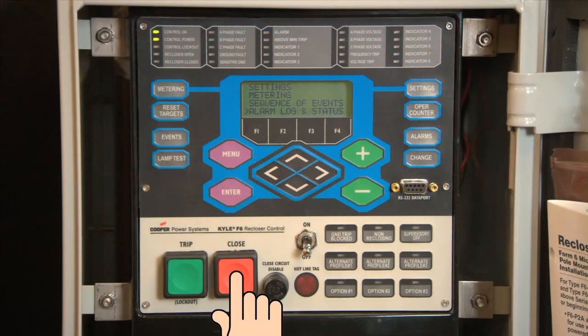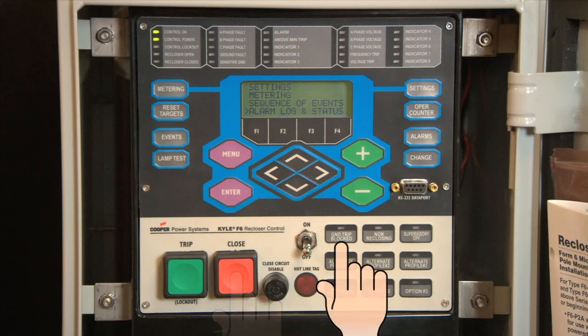Close Push Button. When pressed, the Close Push Button returns the control to the initial or home position, closing the recloser. The control is ready for the start of a new trip close sequence. The ground trip blocked function blocks all ground sensing in the control for the active profile. This red indicator is illuminated when ground trip block is activated from the serial port, input-output, the interface software, or locally, causing the control to block all ground sensing.